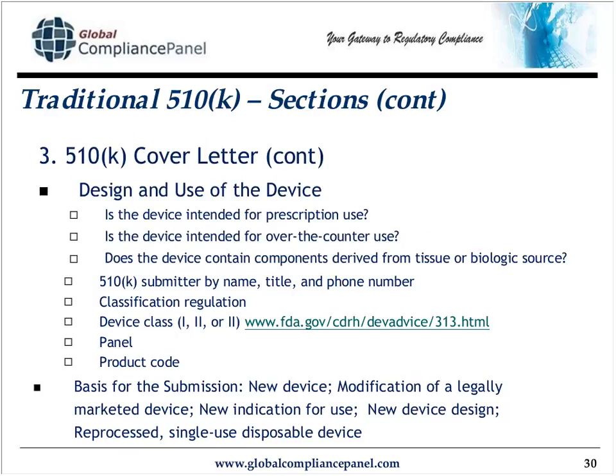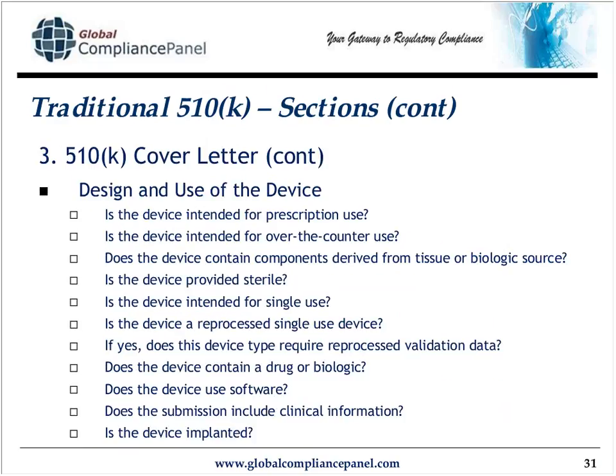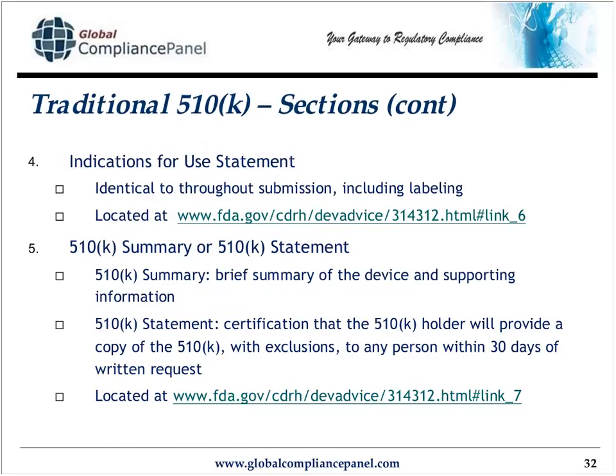Just something to give the reviewer a heads up as far as what to keep an eye out for. The next section of the cover letter is the design and use of device. And I've got to answer each of these questions. I'll just pretty much copy, paste, and write yes or no after each of these. Section 4 is the indications for use statement. Here's its location also. Make sure when you populate the indications for use statement that the wording you use is identical throughout the submission, including on your proposed labeling.